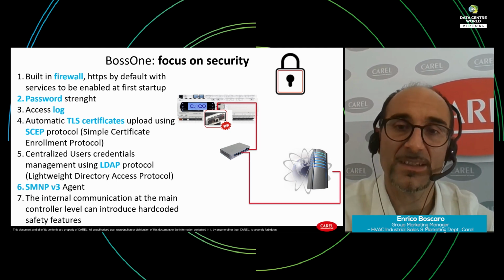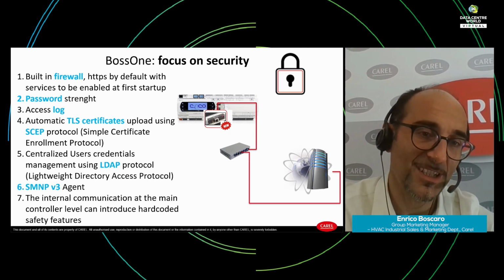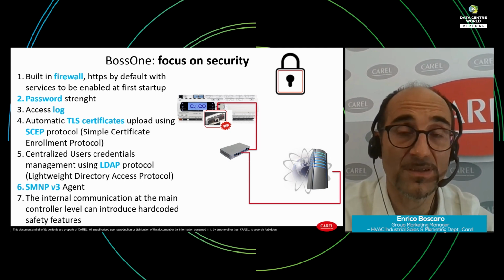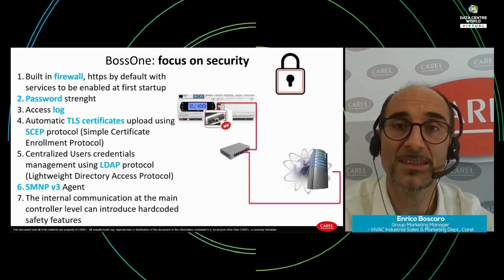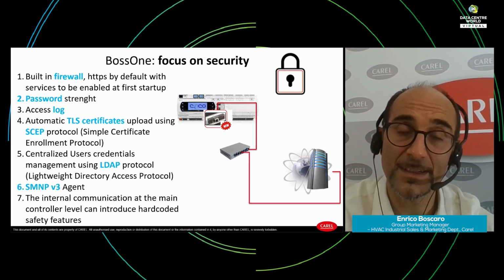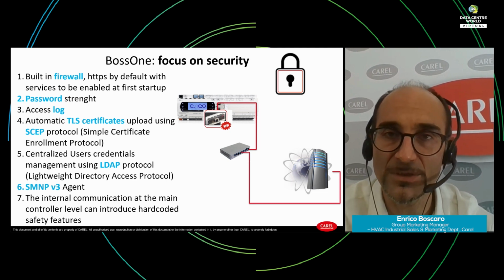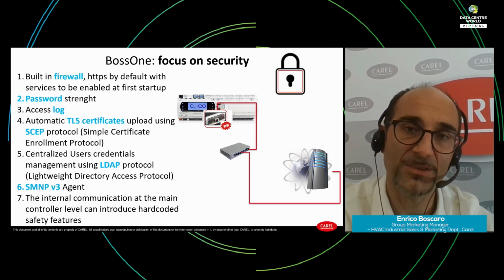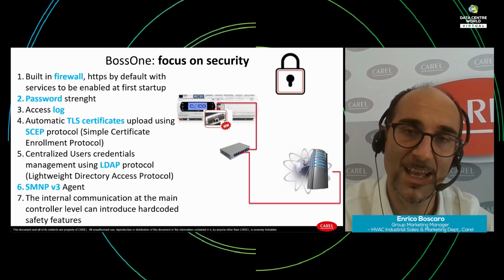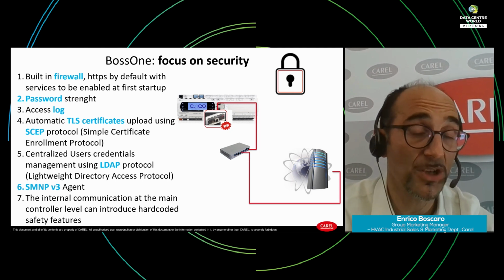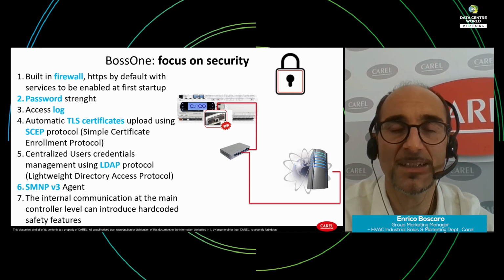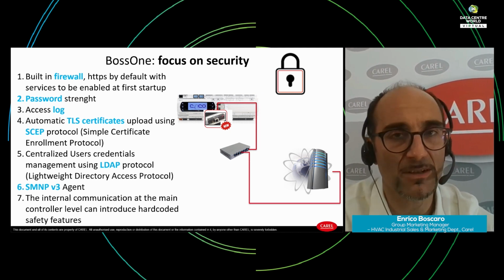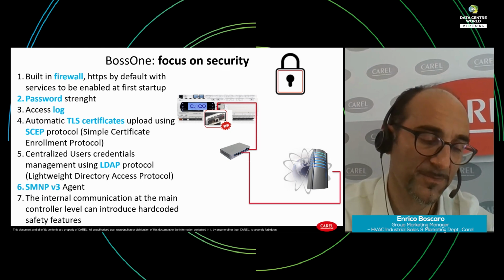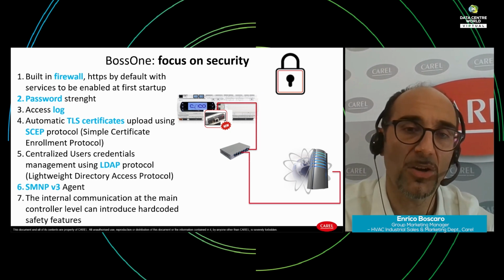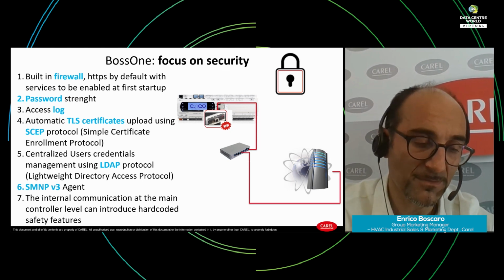Something I mentioned before, the fact that it's separate, it's an edge, it's a separate device, allows you also to have redundant logic that is filtering messages from that edge in order to guarantee continuity on the main controller. You can destroy the edge, but still have some backup procedure to keep the unit running, even if it's not required - maybe it's not energy saving, but it's definitely safe, and it's adding one level of redundancy and security.